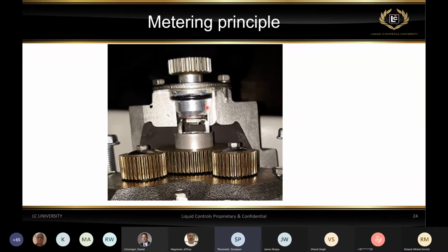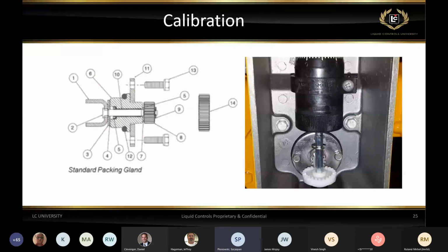The packing gland is designed to contain the pressure. You can see the O-ring here that seals and prevents product from going around the packing gland, and the shaft inside of the packing gland also has a U-cup seal that prevents product from leaking through it. This is probably another view of the packing glands. Again, this part, the fork, in some meters there will be a blade drive, engages directly with the meter shaft and transfers that movement to the outside. On the outside of the meter, we have the gears. And you can see on this picture the packing gland gear, right here behind, engaging with what we call a phase gear.